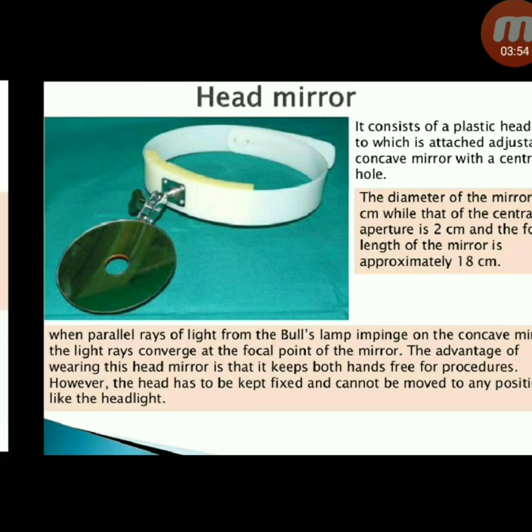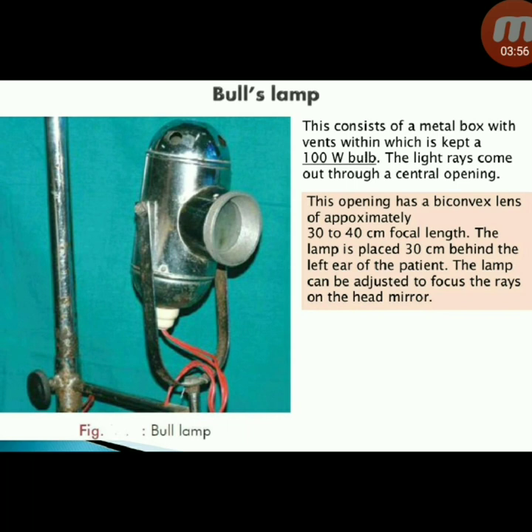Next instrument: bull's lamp — consists of a metal box with vents within which is kept a 100-watt bulb. Light rays come out through a central opening fitted with a biconvex lens of approximately 30 to 40 cm focal length. The lamp is placed 30 cm behind the left ear of the patient and can be adjusted to focus rays on the head mirror.